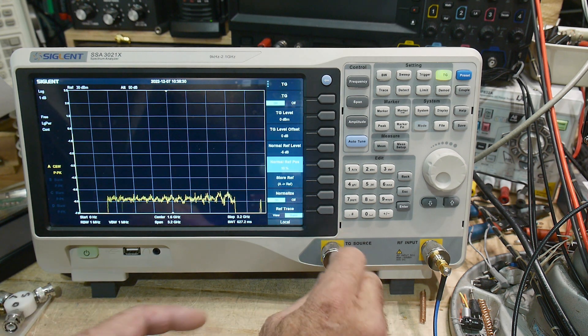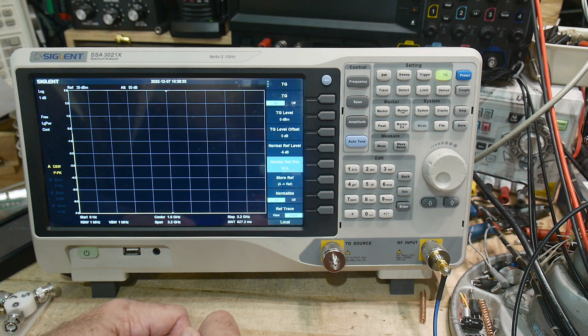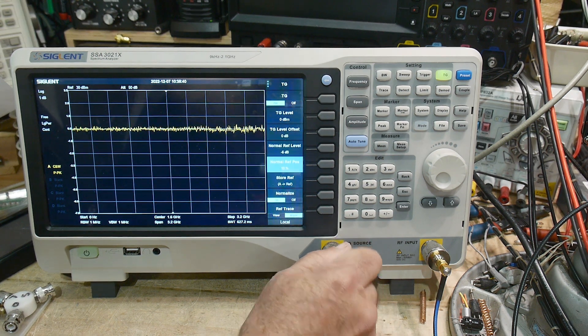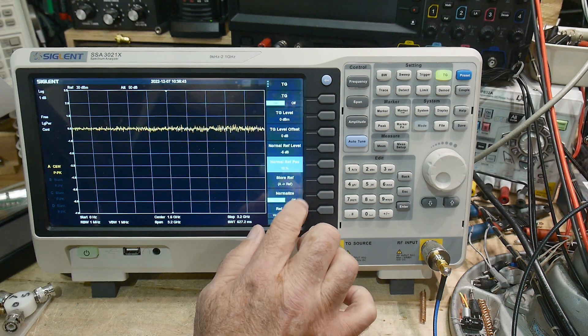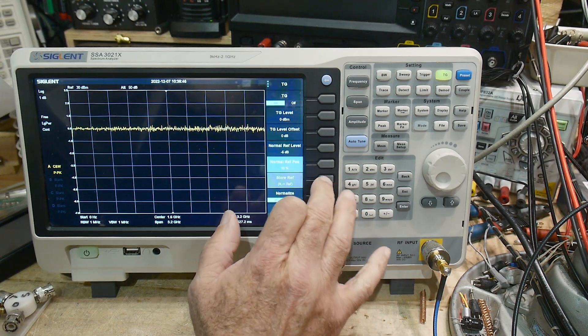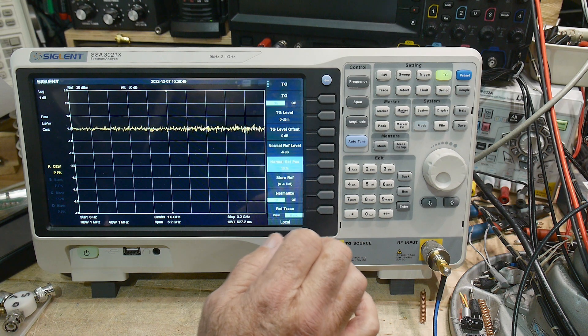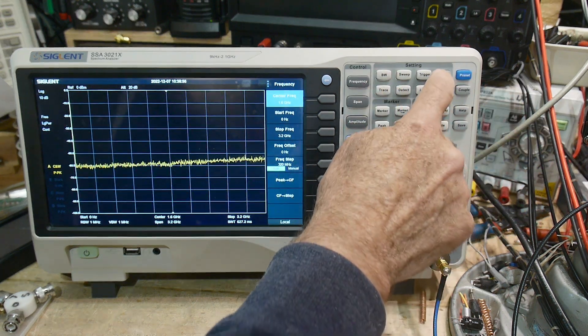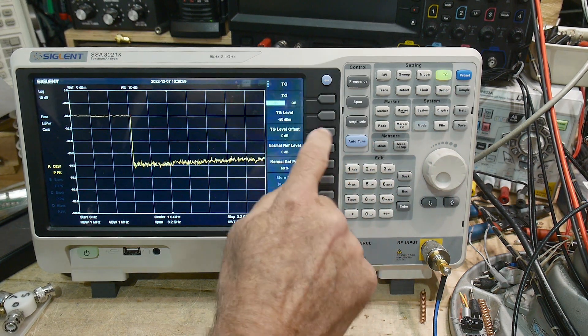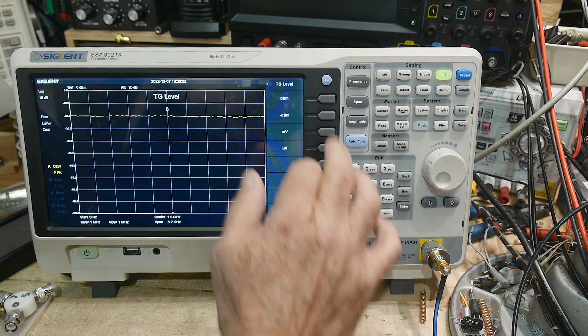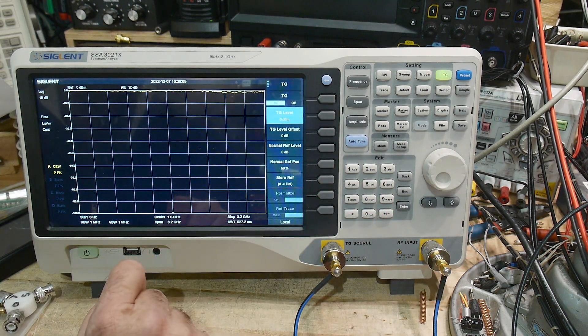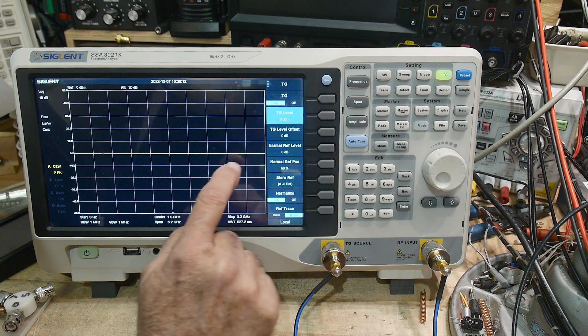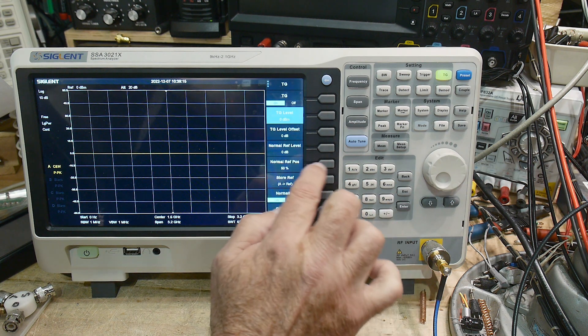A lot of times when you're doing attenuation, let's remove the attenuator again and we will go through the process again. We will say we want to store the reference A, and we want to normalize. Let's do a preset, let's go back to zero because everything's kind of messed up. We'll do a preset, turn on our tracking generator. We'll turn the generator on, we want to have 0 dBm, and it's up there at the top.